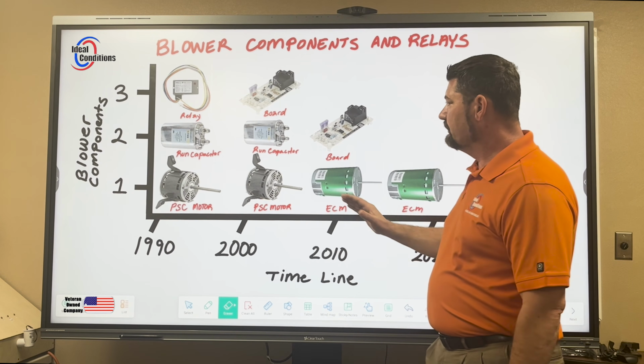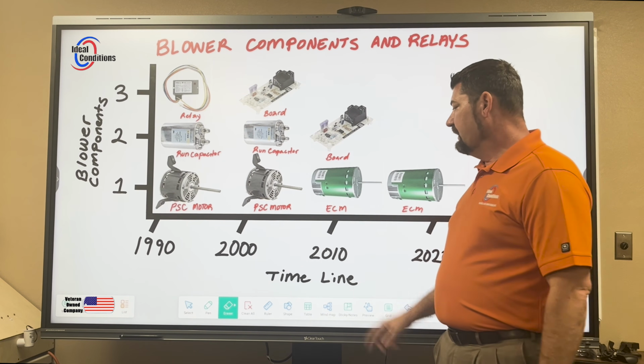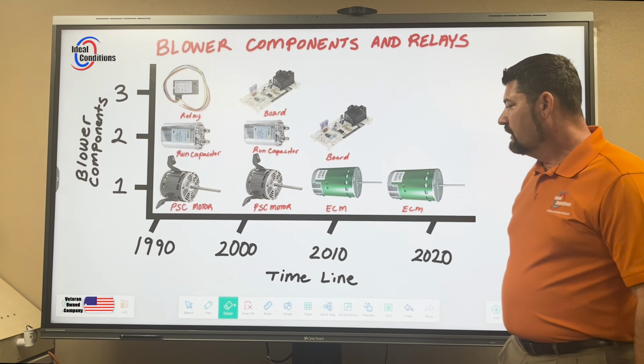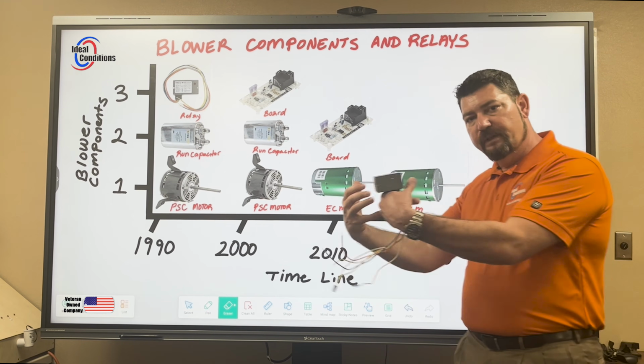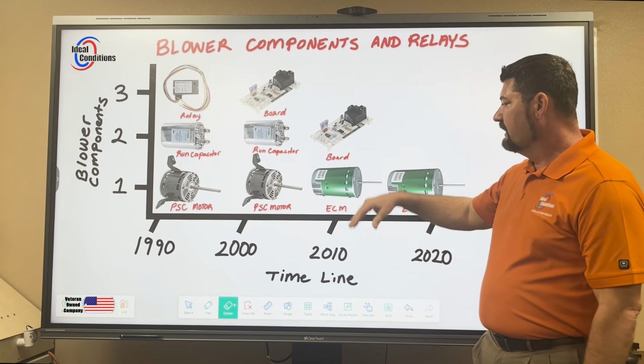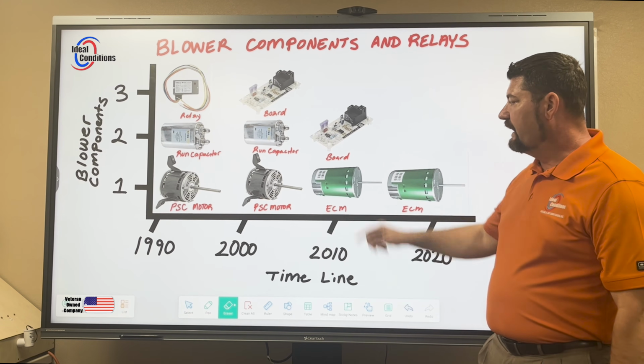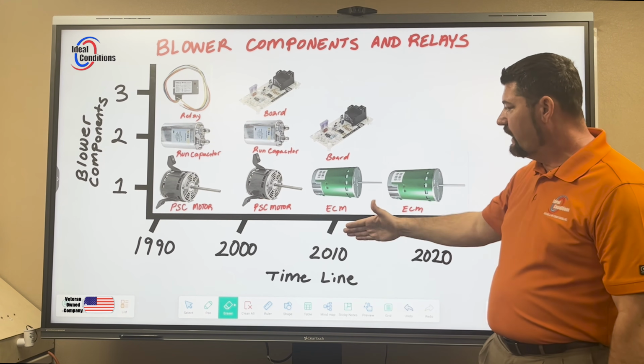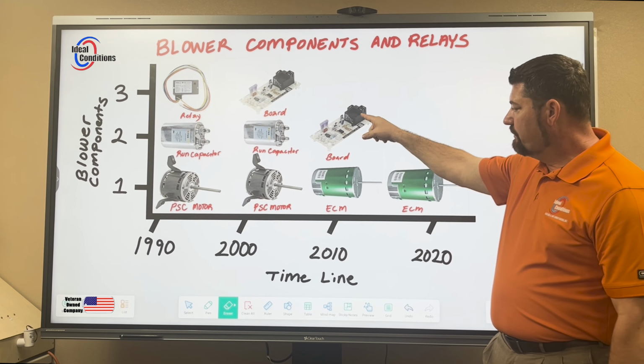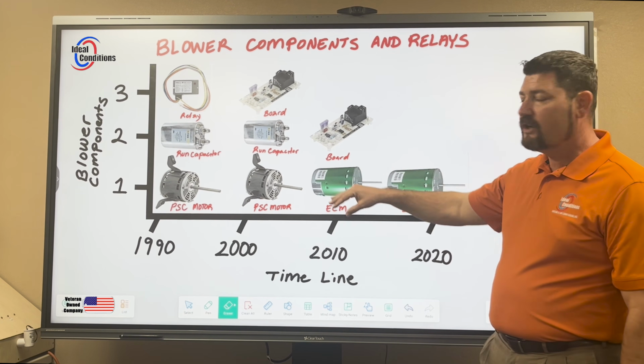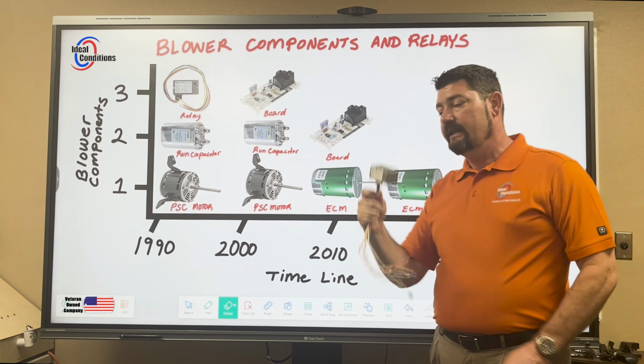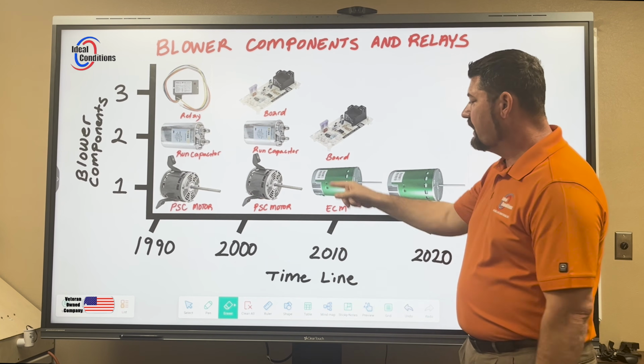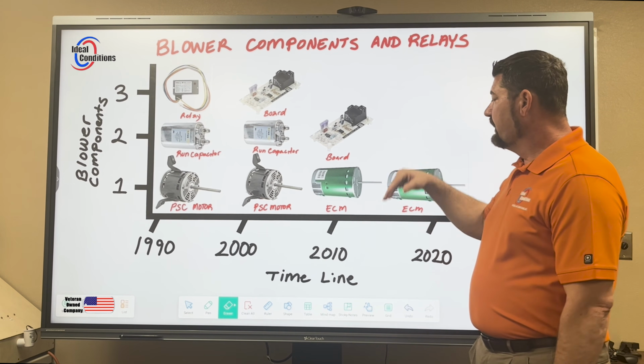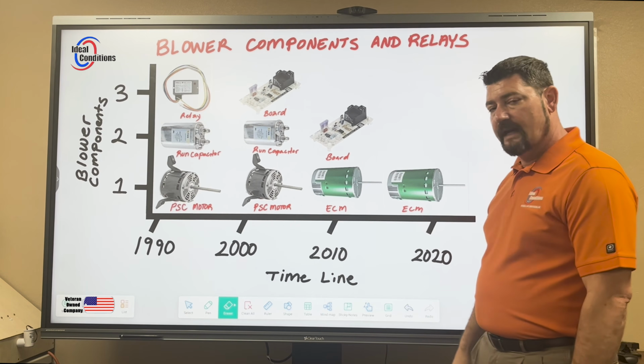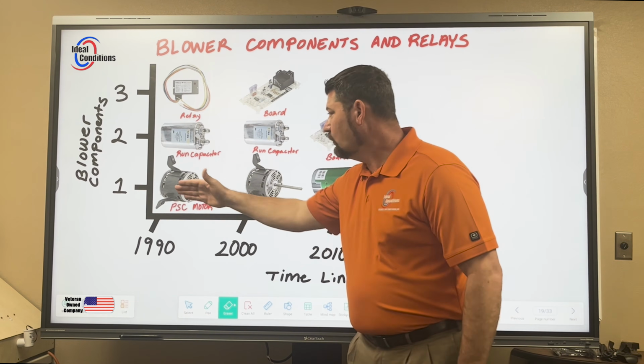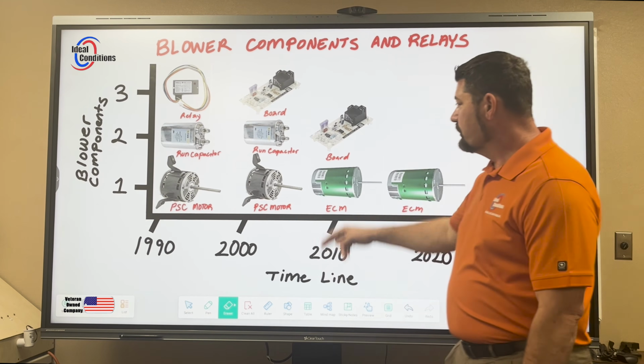As we progressed down the timeline, they said you don't need these capacitors anymore. These ECMs, these electronically commutated motors, they now have capacitors built into it. We call it the module, and inside of that, everything is there. All you needed was a relay, which if you're in this situation and you're not getting the relay portion to come on, but the motor tested out fine with the module, then you can simply put even a RIB relay right there, and you can wire that motor up for it to come on. In the event that that wasn't the case, you would have to change your motor out, which you can go back down this way and add a capacitor and a PSC motor, still using your control board.